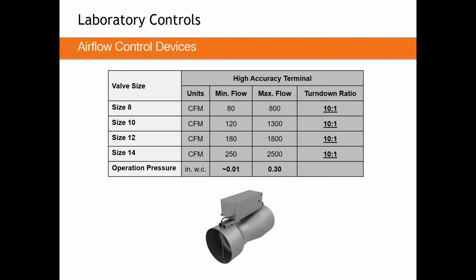Now remember, regardless of the manufacturer, the style, or shape of the valve, that is a minimum pressure drop. So if you call and say, I have 0.3 inches, can I get 800 CFM through a size 8 box? The true answer is yes. But the more appropriate answer is yes, but you cannot control it. You can measure that flow and you can flow it through your system, but you can't control it. If you'd like to control that flow, you need more pressure.